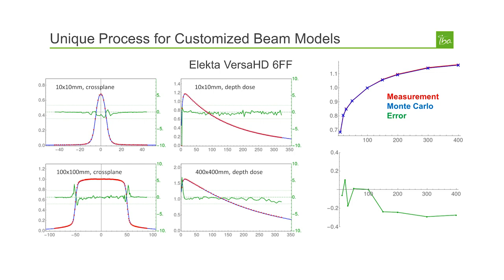The example shown here is an Elekta Versa HD accelerator with a 6 MV flattened beam. On the right side we see the output factor curve with an error on the order of 0.2%, which is very close to the output factor stability of the accelerator and also very close to the statistical uncertainty in the Monte Carlo dose computations. In the center column we see depth dose curves for a small 10×10 mm field and a maximum 400×400 mm field, with errors well below 1%. The left column shows cross profiles for very small and very large fields with very high accuracy.